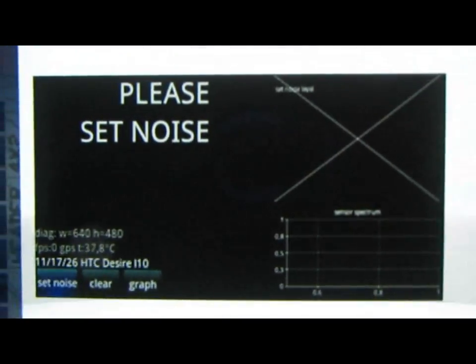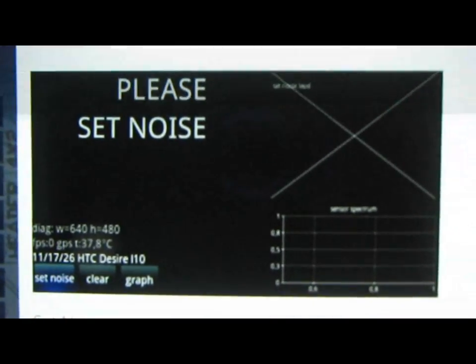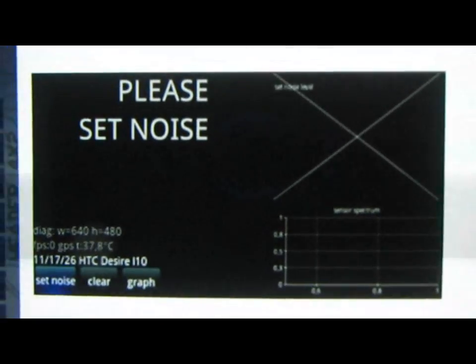The calibration will take quite a long time - maybe 10 to 15 minutes. It performs repetitive one-minute measurements, then starts again and tells you to please wait. That's totally normal, and after that your device will be calibrated.